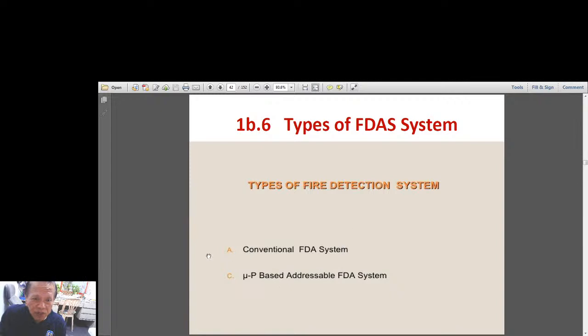One is the conventional type, and the other one is the addressable type. The difference between the two is that the conventional type is an analog system. So it works like on a switching, like ordinary relays and ordinary switches. While the addressable type works with computers, so it has a central processing unit and a video monitor, and the detectors are all using digital communications, and there is the binary system that is being used between the detector and the computer system.